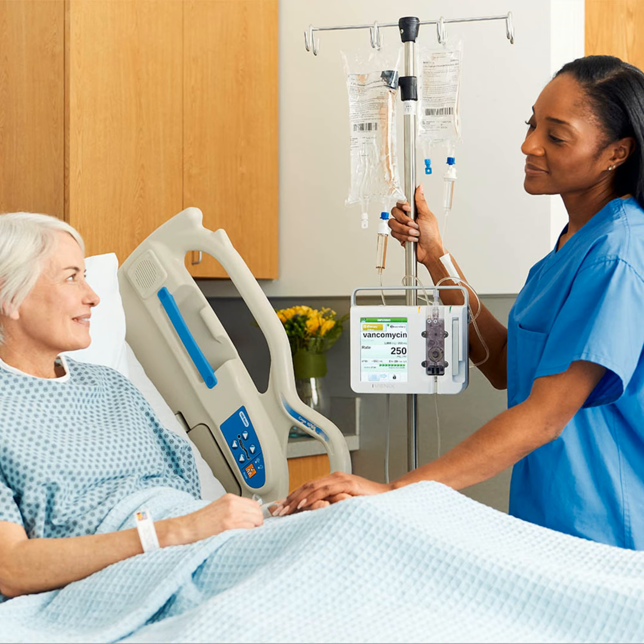Now, in all of this usability, I haven't even mentioned those excess alarms, which can lead to fatigue, which is another source of stress for the nurse. And all of these issues can be exacerbated in the critical care units like ICU, where nurses experience even more high cognitive drain, and the pump use is especially high, especially when you have multiple pumps compared with the patient. And so all of this leads us to why advanced technology is needed. Number one, to lower the complexity, to lower the cognitive demand, to lower the potential for contributing to medication errors. So next, let's talk about secondary infusions.